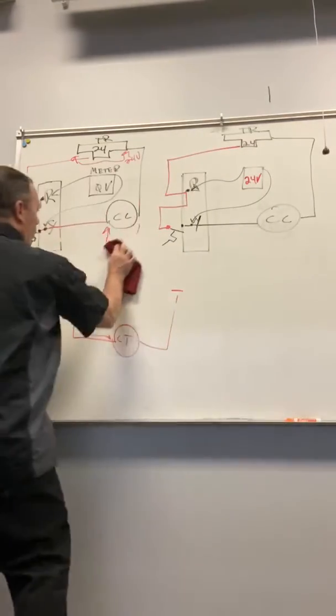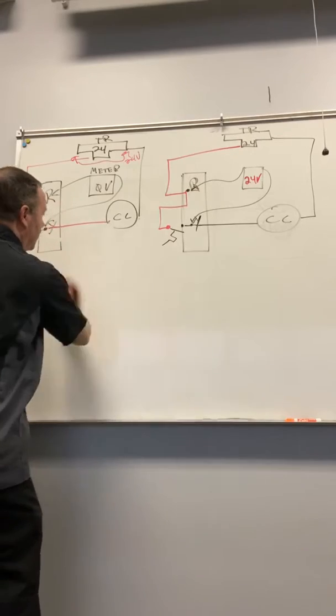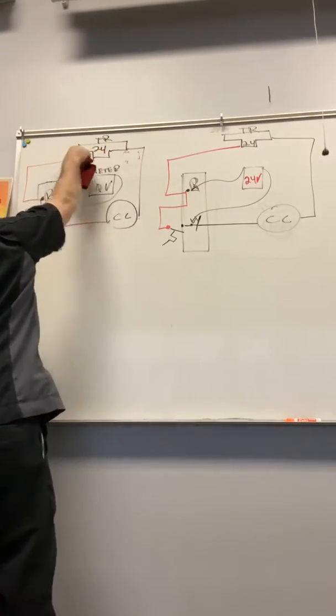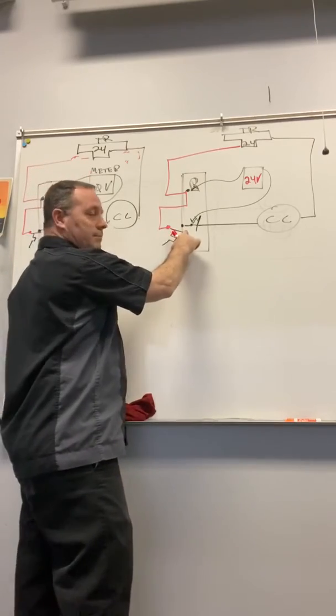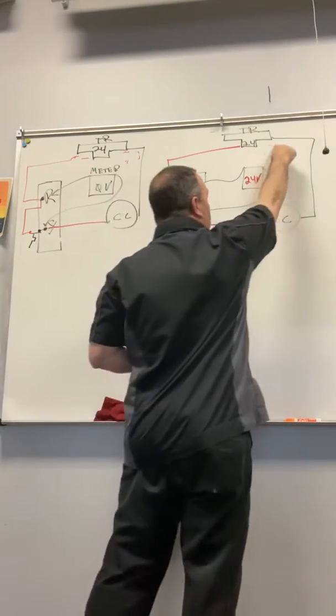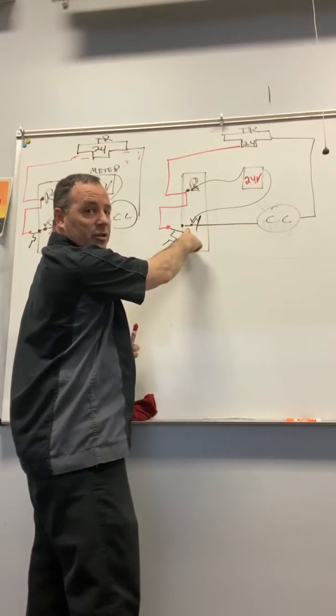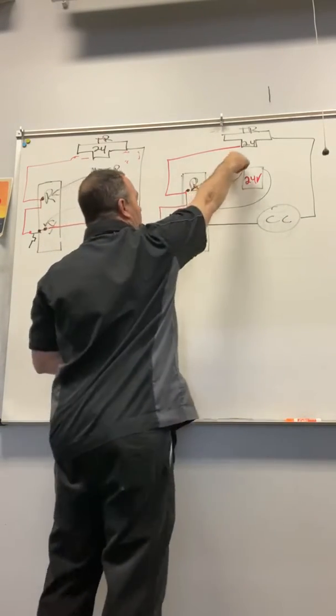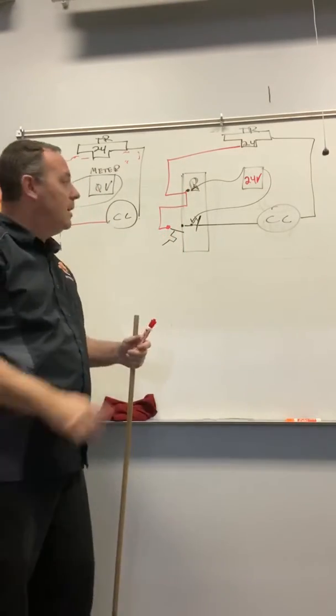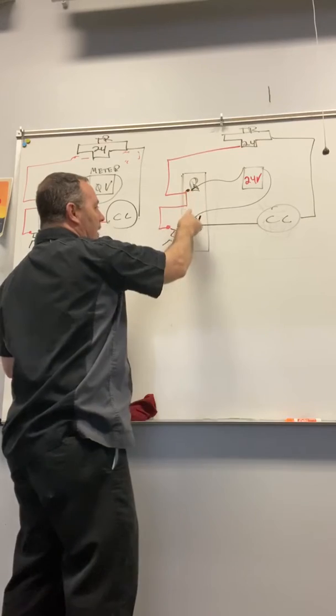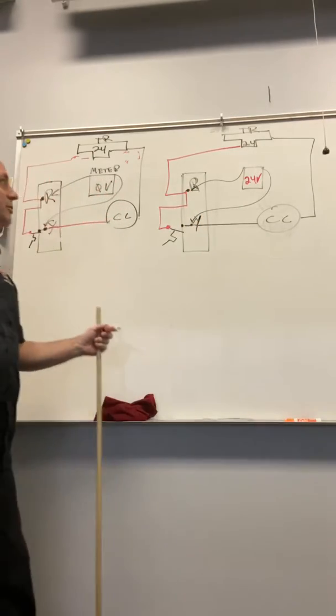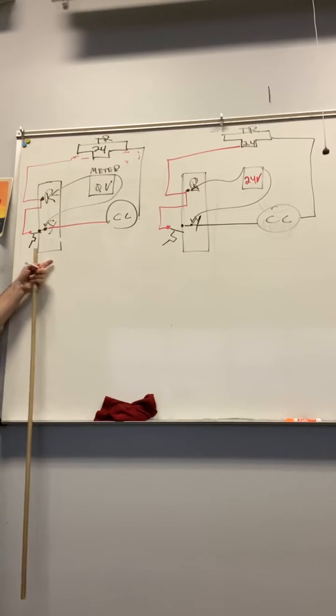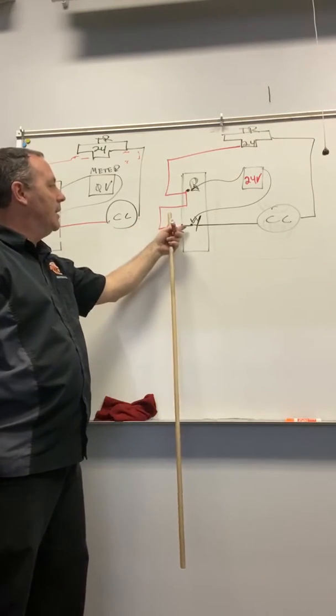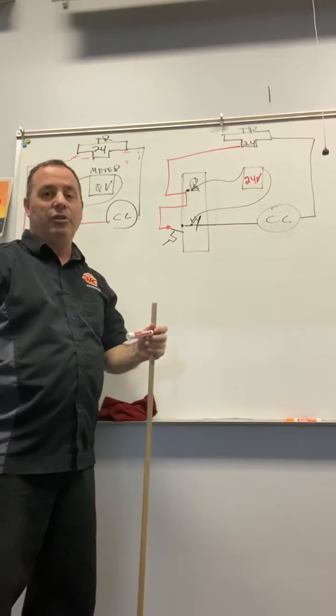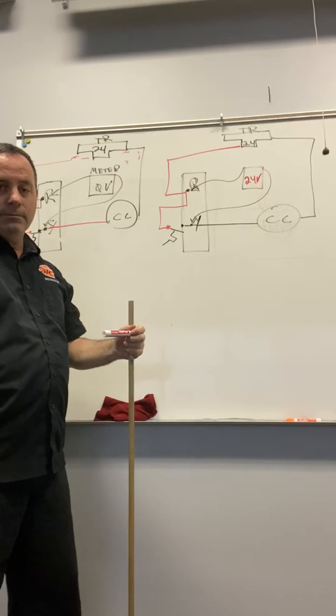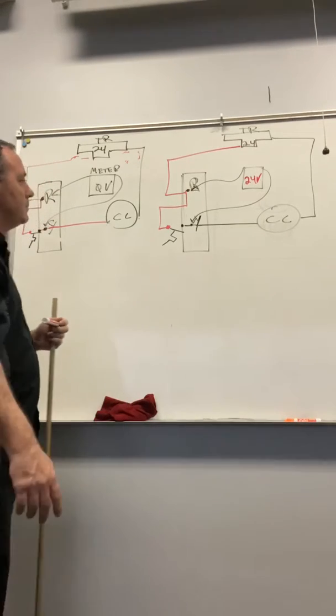But what if the circuit's open? Now, as you can see, I'm on this side of the circuit at Y. Here, I got power here. So now, between R and Y, I'm reading 24 volts. See the difference between the two? R and Y, when I'm reading 24 volts, means the circuit's open.